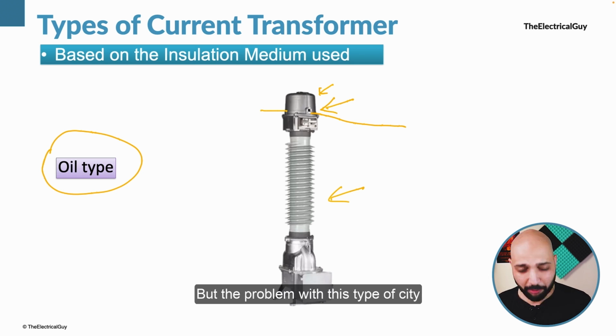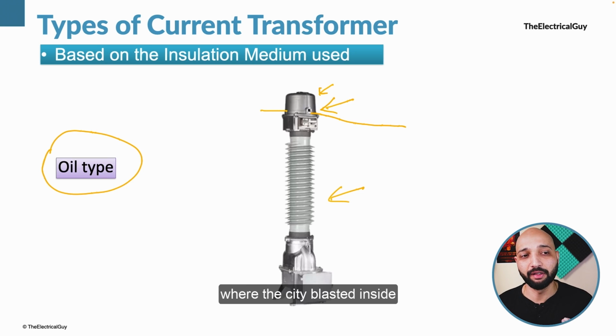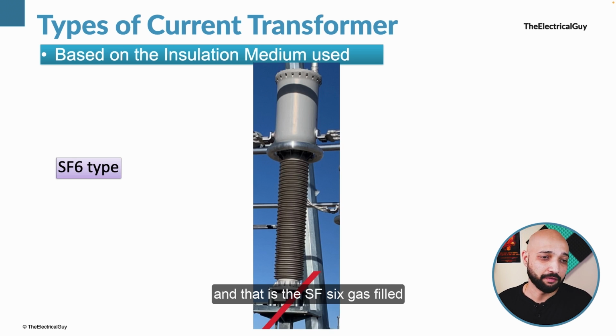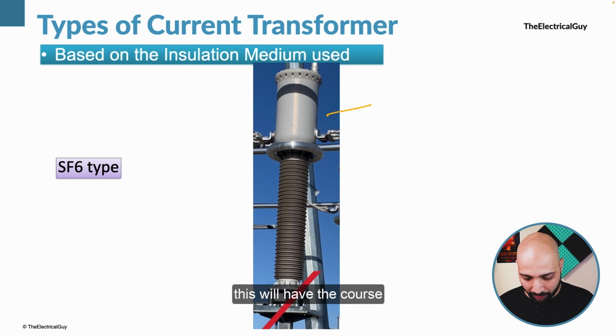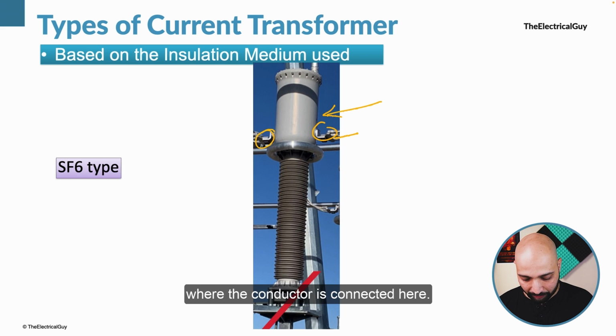But the problem with this type of CT is that the oil is not very reliable, and there have been a lot of incidences where the CT blasted inside the substation. And this is not a very reliable type of insulating medium. But since it is cheap, cost-wise, it is very widely used. There is one more alternative we have here, and that is the SF6 gas-filled current transformer. Now, this is more reliable and secure when we compare it with the oil-type current transformer. So, you can see the image here. Again, this will have the cores inside this tank. You see the terminal pads are coming out where the conductor is connected here.